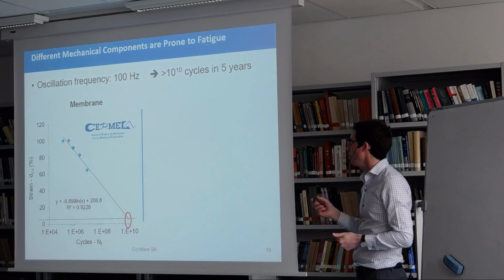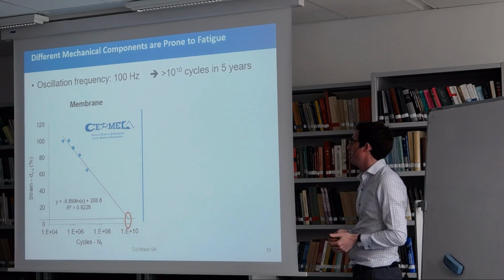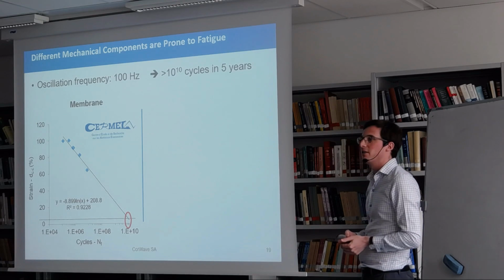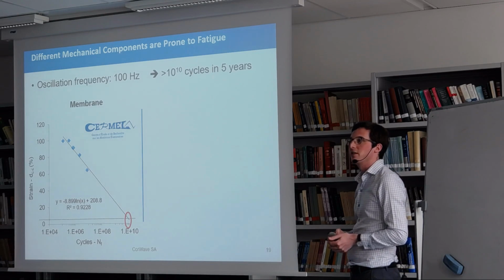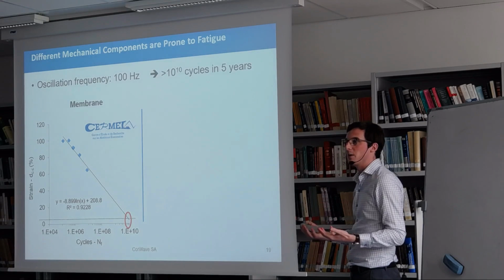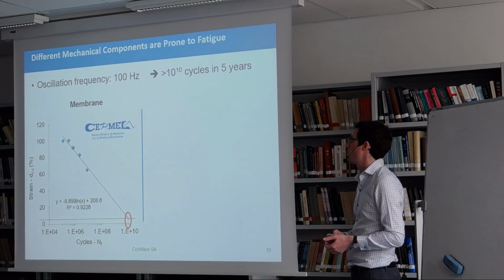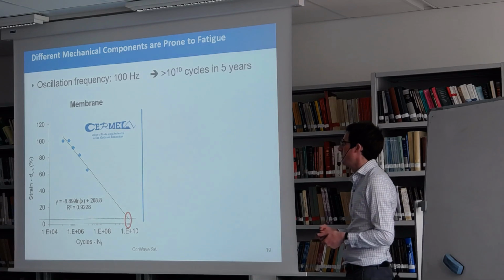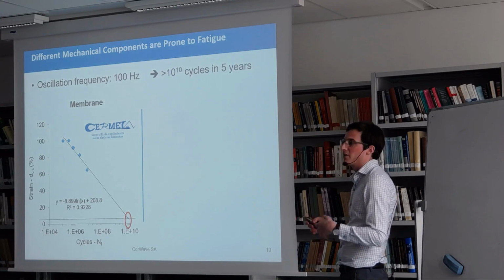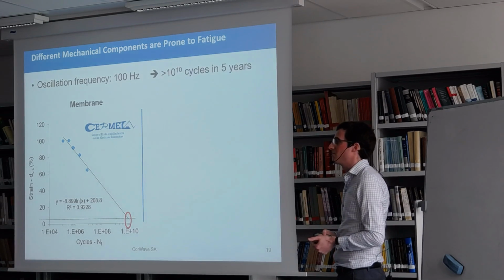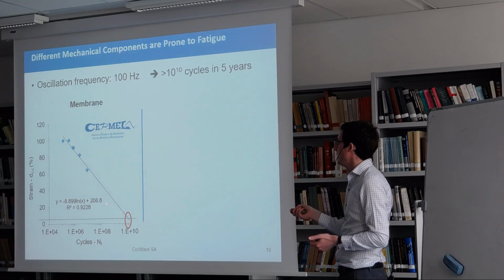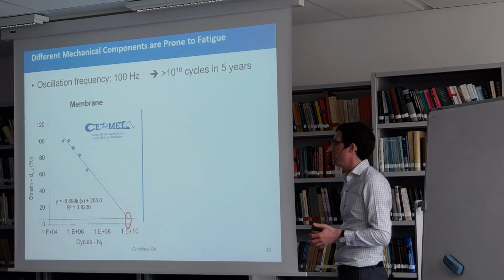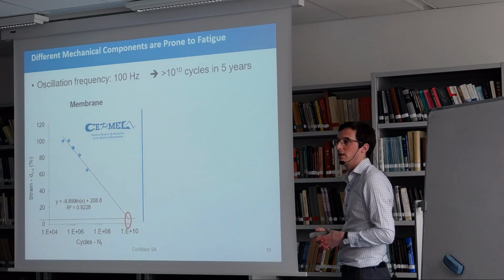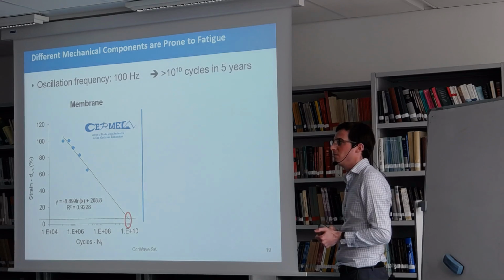So on the membrane side, we're collaborating with Cermel to evaluate how much strain we are allowed in the membrane, so we would assure infinite lifetime, or at least 10 billion cycles. By this accelerated testing, by straining them more, we can extrapolate that, well, if we keep our strain under 5%, which we do, from a purely material point of view, the material should be able to last.